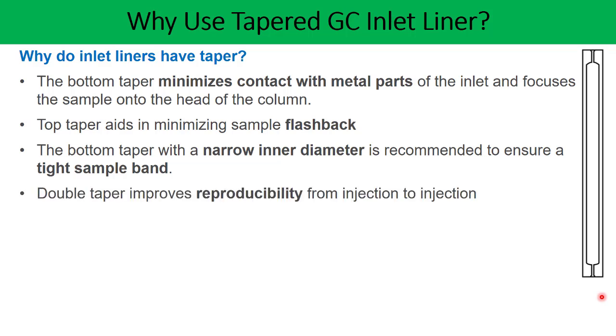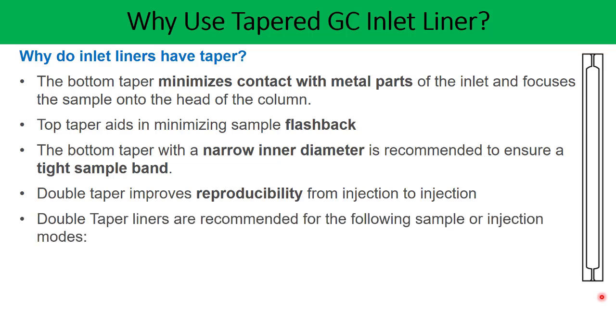Double taper improves reproducibility from injection to injection, because it avoids loss and improves the consistency of the sample going onto the column, especially in the case of splitless injection mode.